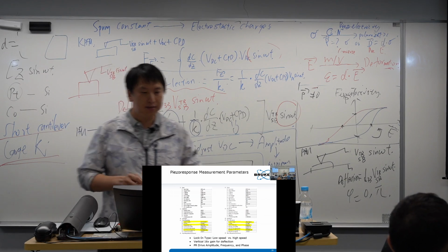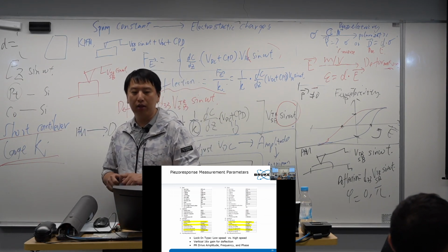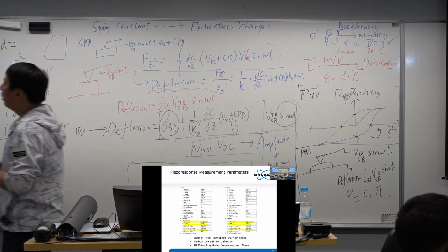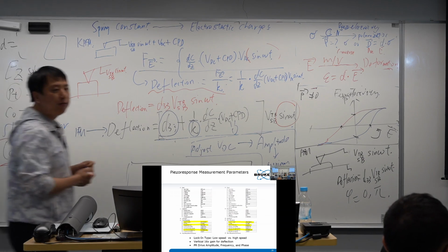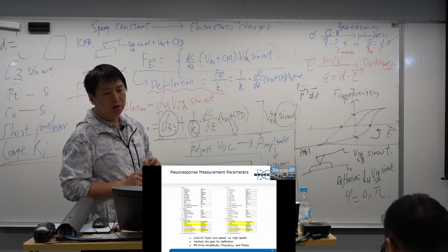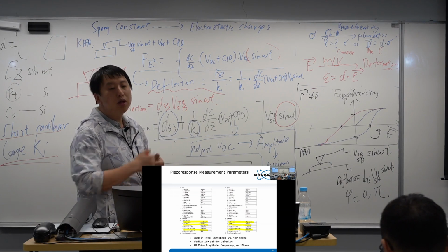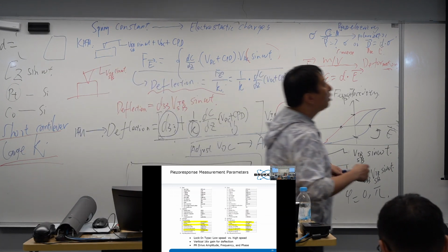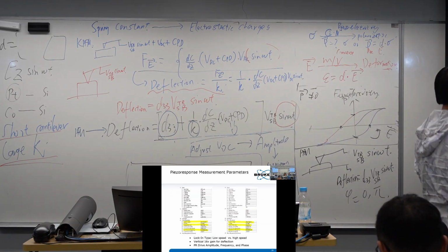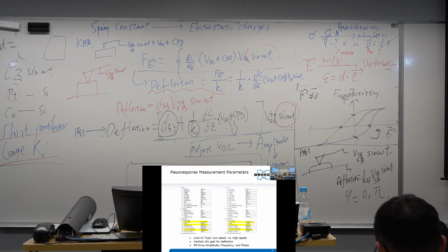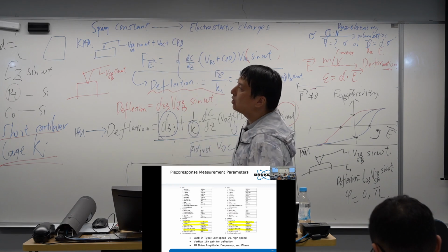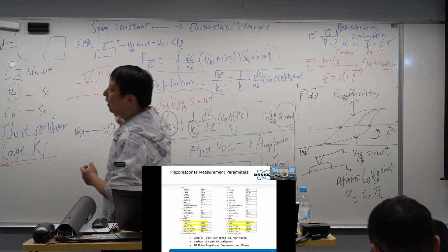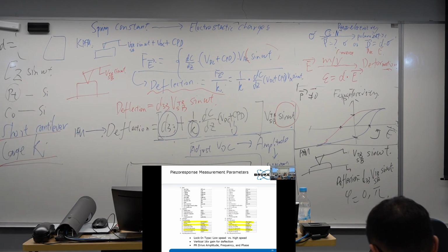Okay, so the next thing is about the instrument itself. In the afternoon, we will show you two types of PFM working modes, or what we call workspace. The one we call optimized vertical means it's specially designed to detect the D33, to detect the Z direction. So it's optimized to detect the vertical. It gives two types of frequency range.